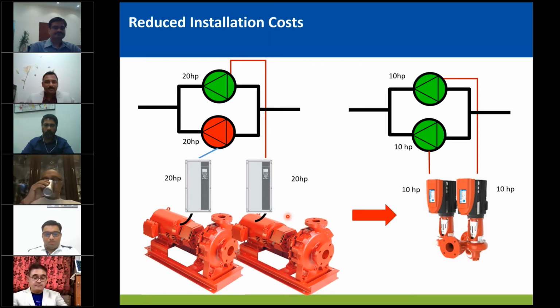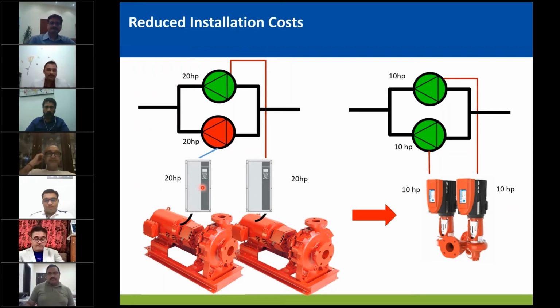Let's talk about the sizing of the pumps. So 100% flow, 100% duty standby, 20 HP running, 20 HP standby, needs a 20 HP drive, variable speed drive. And if you look at 50% flow rate or capacity, you only need 10 HP each. So that further reduces initial cost of the project.